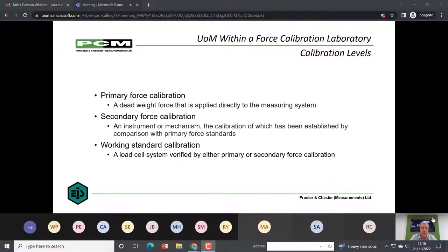Secondary force calibration is a device that's had a calibration carried out by primary force, and then you have a working standard calibration, and that's typically the kind of products and services that we provide to calibrate in an industrial environment.